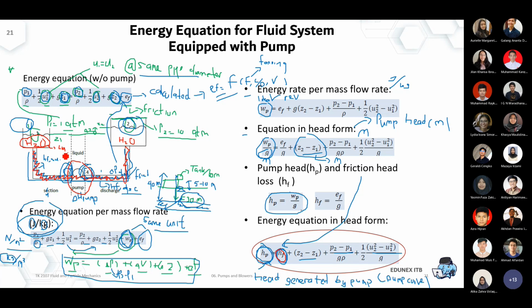Sometimes we miscalculate, we misunderstand some part. Even though our tank is already in liquid form, what actually matters for the NPSH calculation is what happens at point 3. That's the reference point for the NPSH calculation, net positive suction head. Why? Because what you have to ensure is you don't have any vapor at point 3, not at point 1.